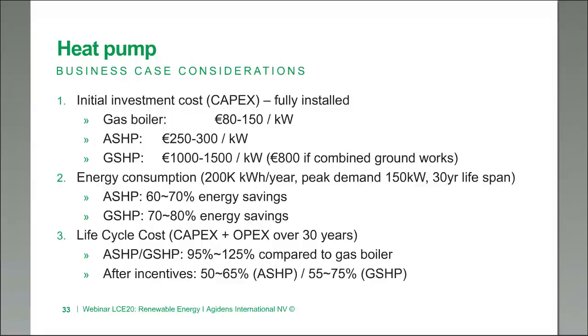Comparing energy consumption of these three systems based on 200,000 kilowatt hours per year with a peak demand of 150 kilowatt and a 30-year lifespan: the air source heat pump can provide operational energy savings between 60 and 70 percent, and the ground source heat pump goes even further with savings of 70 to 80 percent. However, the impact on the total life cycle cost — looking at both CAPEX and OPEX over 30 years — shows that both air source and ground source heat pumps end up costing as much as 95 to 125 percent compared to a gas boiler.